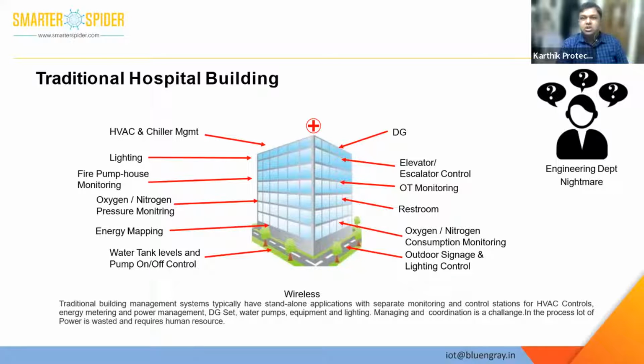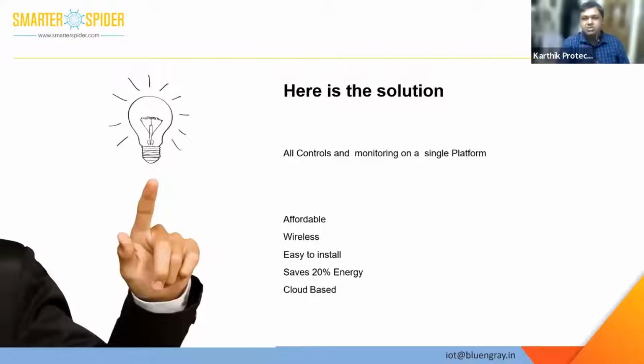Now, monitoring and controlling all these utilities is a tedious task for the engineering department or the facility management, as they are dependent on manpower for either monitoring of these utilities or on-off of these utilities. In this process, a lot of energy gets wasted. For example, clogging of the filters is one of the challenges in some of the hospitals where we have done automation, which we found, and then more runtime, like instead of running between the fixed duration, it is running before and beyond the particular time. So considering all these challenges, we have a solution where all controls and monitoring is on a single platform.